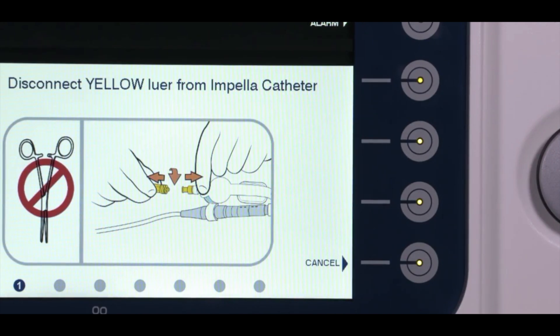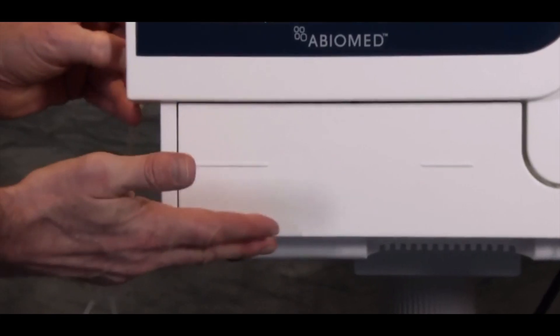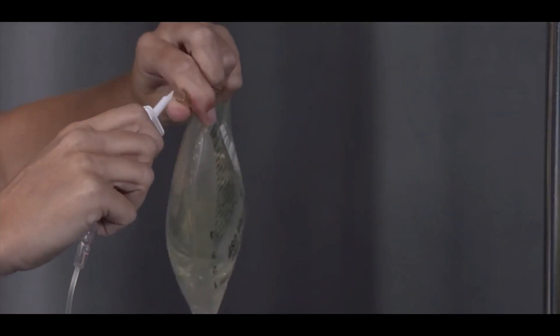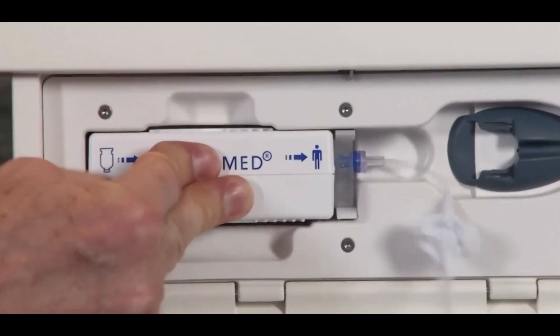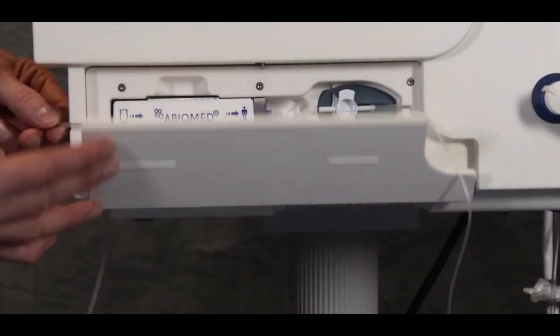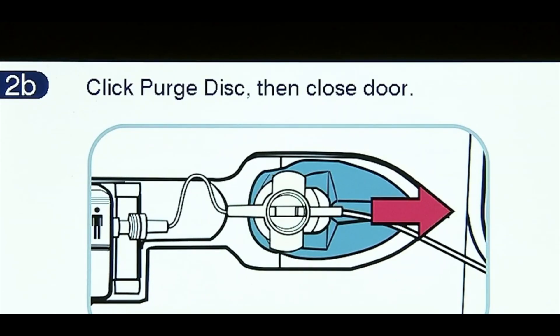Disconnect the yellow luer from the Impella catheter. Do not use a hemostat to disconnect the luer as this could damage the Impella catheter. Open the purge cassette door by pressing the button on the left side of the AIC. Remove and discard the old purge cassette and purge fluid bag. Spike the new purge fluid bag with the new purge cassette and press the next soft button. Insert the new purge cassette with the Abiomed logo facing outwards. Slide the purge disc into place until an audible click is heard. If this is not completed within 10 seconds, an animation of correct insertion will be displayed. Once the purge disc is inserted, the AIC will automatically advance to the next screen.